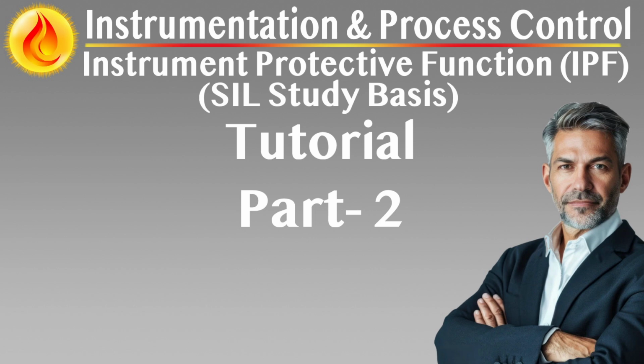Determine logic solver cycle and scan time. The safety system must process input and output logic without delay that infringes on PST margin. Establish minimum test and diagnostic coverage. Fast-developing hazards require more frequent testing and reliable diagnostics to avoid latent failures.